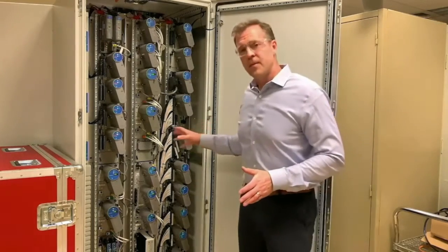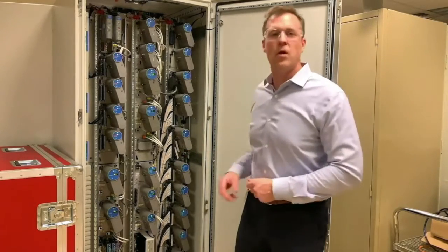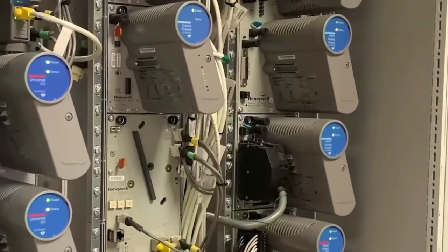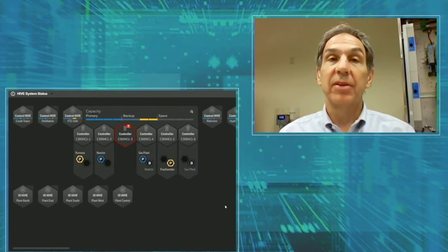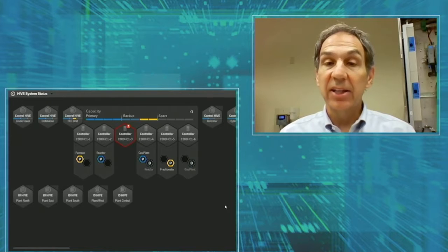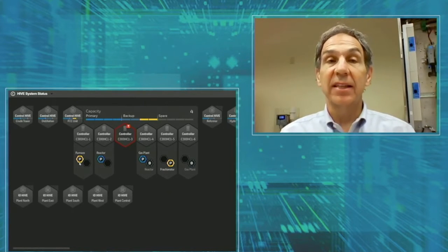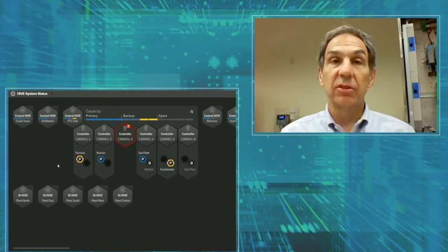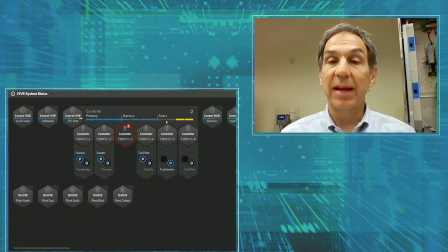Let's start by simulating a fault by simply removing one of the controllers that are running under power. The system view clearly shows the Control Hive behavior. On controller failure, the backups of the affected primaries immediately assume control, as seen here for the Fractionator on controller 5. The Fractionator and Furnace CEs are highlighted in yellow while their backups are established and synchronized, after which the Control Hive returns to a fully backed-up state, with a reduced spare capacity as indicated in the capacity summary.